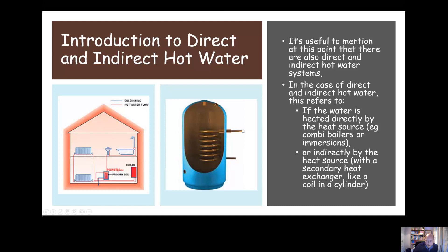An indirect hot water system has a secondary heat exchanger — a coil inside the cylinder. The boiler heats water which circulates through the coil and returns to the boiler; the heated water in the coil then heats the water in the cylinder. So the water is heated indirectly — the water from the heat source never actually comes out of our taps. We don't want to confuse direct and indirect cold water with direct and indirect hot water.